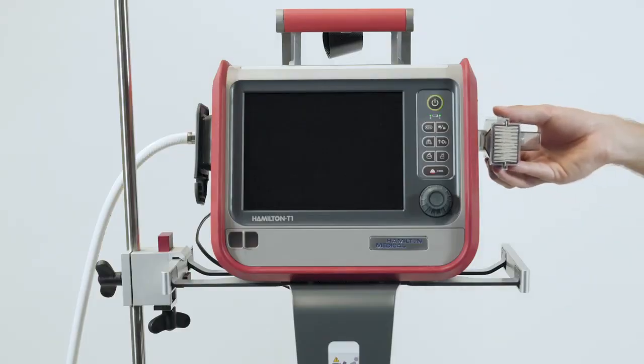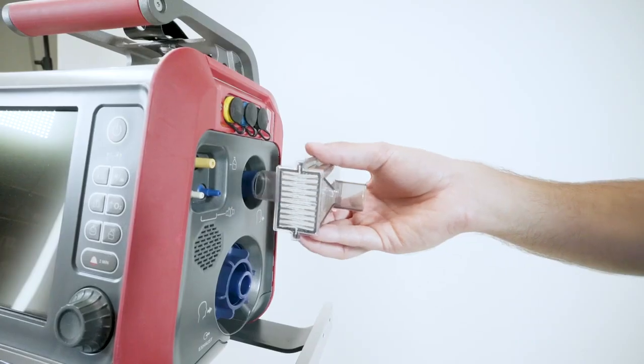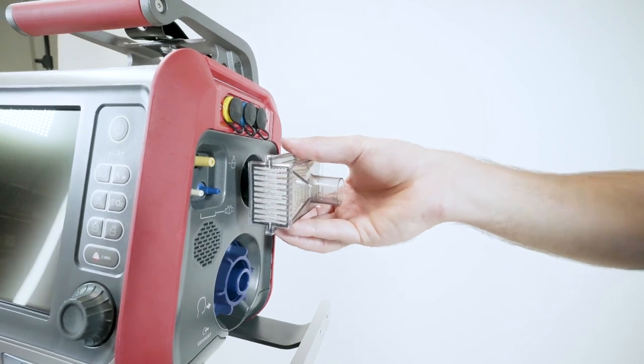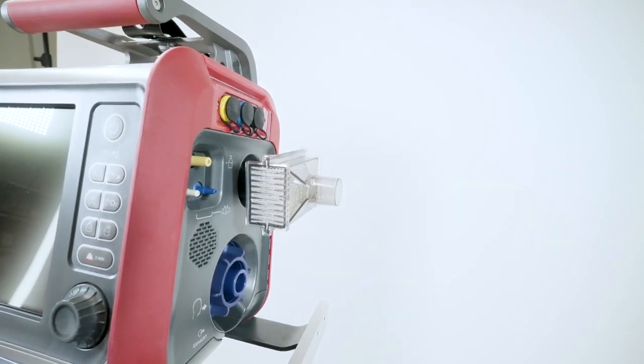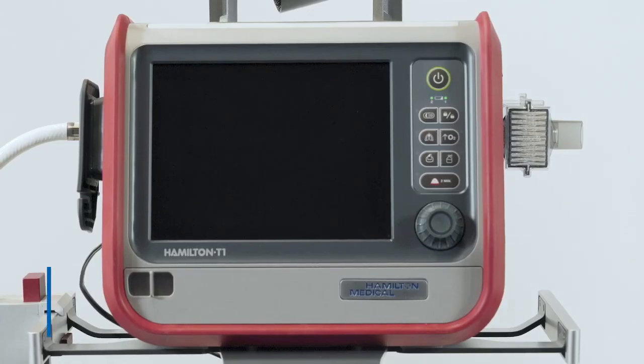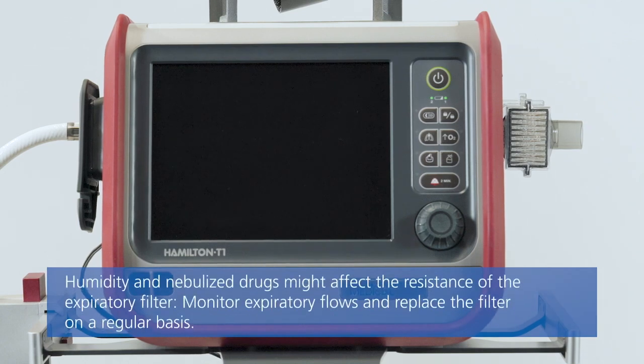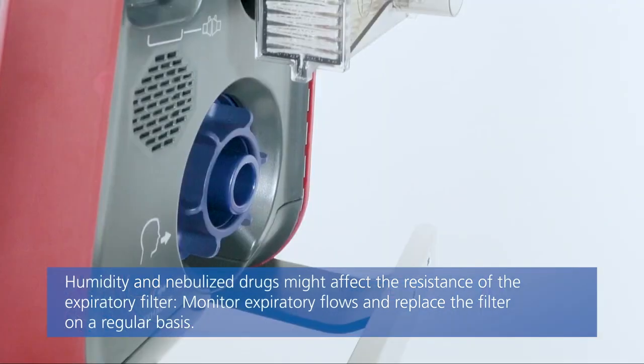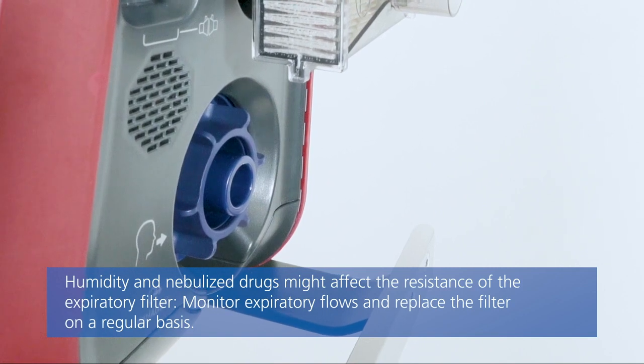To prevent patient or ventilator contamination, connect a bacterial and viral filter between the patient and the inspiratory port. An expiratory filter is not required, but you might use one for infection control according to your institution's protocol. If you use one, place it on the patient side of the expiratory valve.